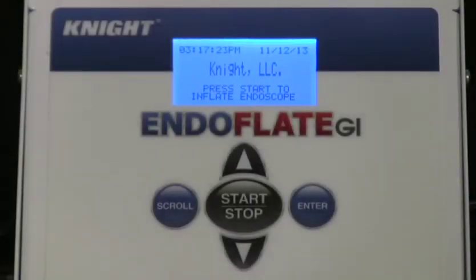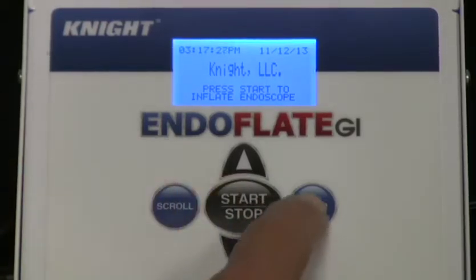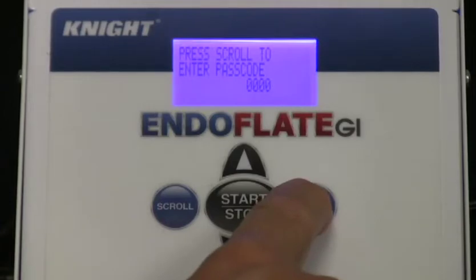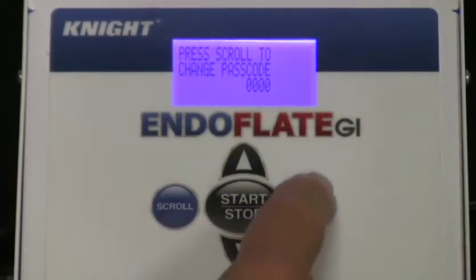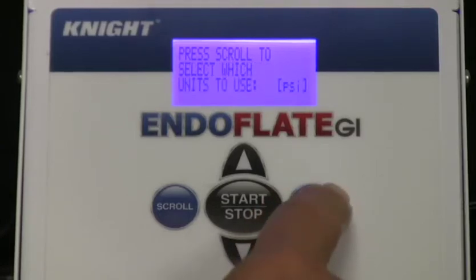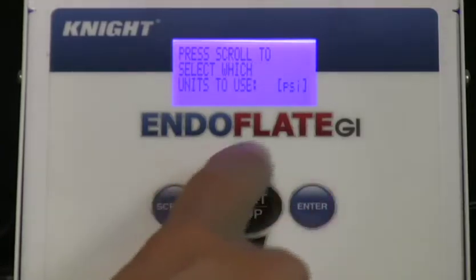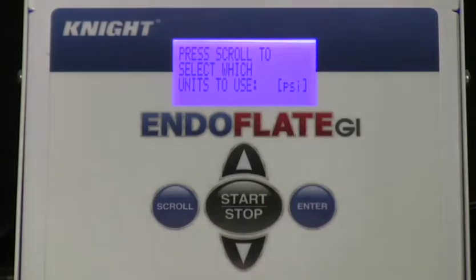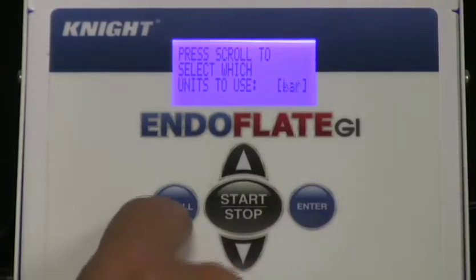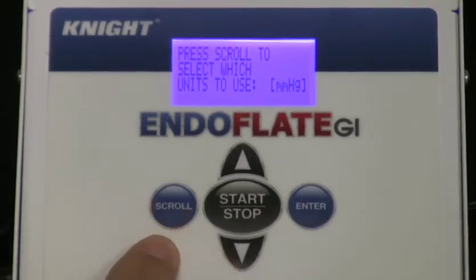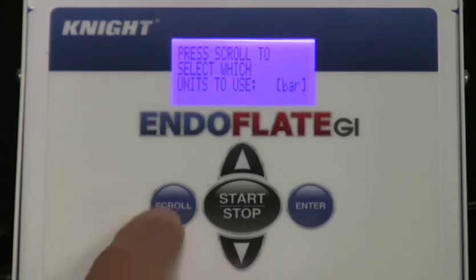So let's just talk about how you program the EndoFlate GI. Hold the enter key down until the screen color changes, and you've got the normal enter passcode, change passcode entries that we see in most of our products. Here you can select whether you want the digital readout to be in US pounds per square inch, or in European bars, or millimeters of mercury. For this demonstration, we're going to run in PSI.